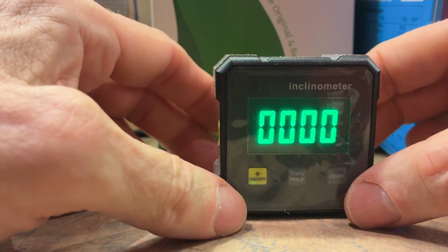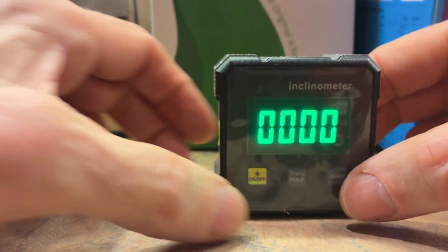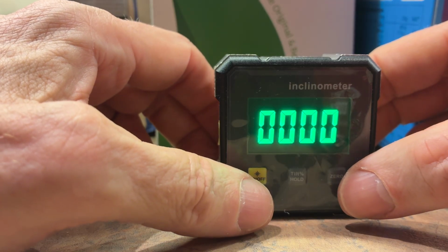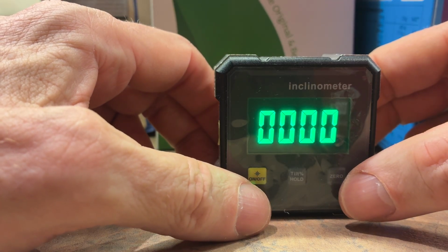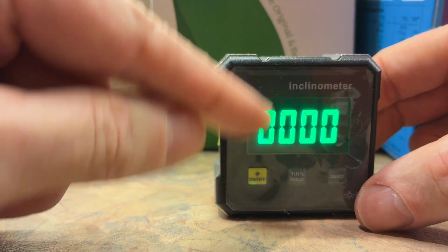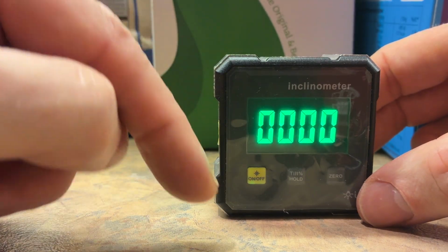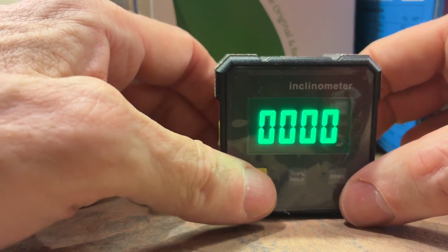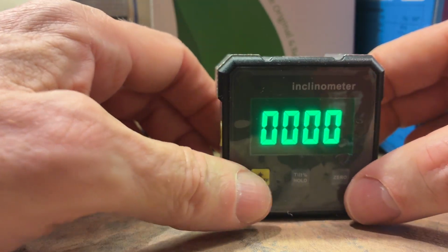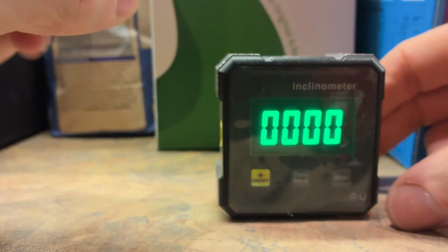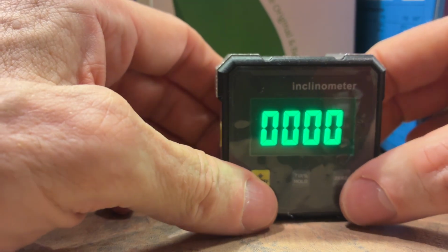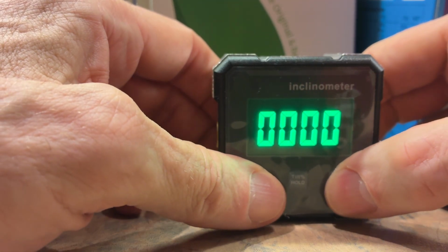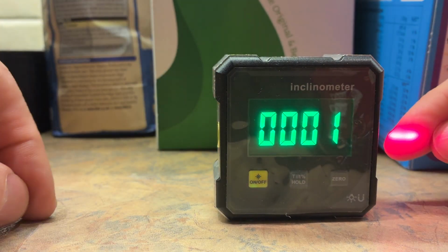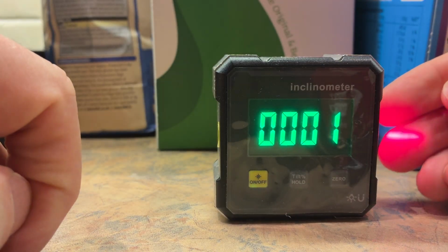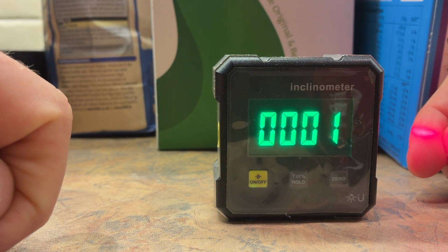So in that position, you press and release the 0 and the on/off, but it's very, very important that you press them simultaneously. If you don't, all you'll do is switch your laser on, or you'll turn the device off, you'll mess it up, you'll have to do it again. If you press and release both buttons simultaneously, the zeros flash about 2 or 3 times, and then you get a 1 to say that it's calibrated in this orientation. So here we go, press and release. And incidentally, can you see it's gone to 1? It has switched the laser on. Ignore that, but whatever you do, don't look into the laser.